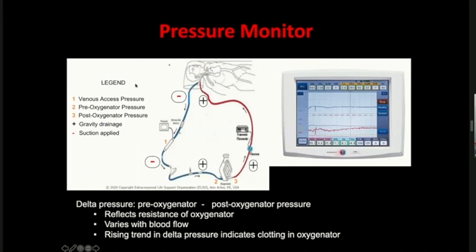The pressure monitor is a very important component for assessing and troubleshooting the ECMO circuit. In this schematic, the patient has a double lumen cannula. The red denotes the return cannula carrying oxygenated blood after passing through the membrane oxygenator, while blue refers to the drainage cannula draining deoxygenated blood. Everything before the pump is negative pressure — the only way blood can be drawn from the patient. Any disconnection in this area will result in atmospheric air being sucked into the system, introducing air within the ECMO circuit.